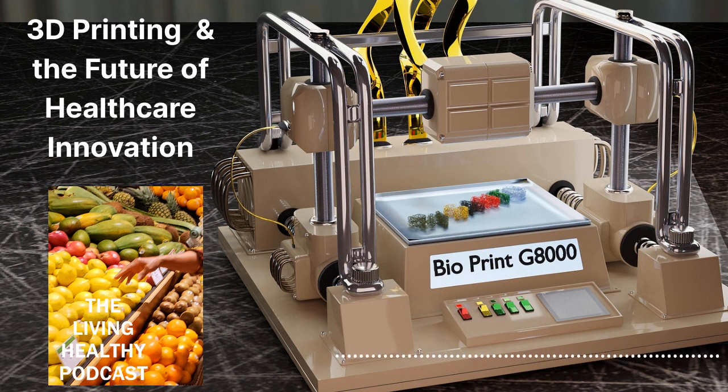As it stands, as of August of 2023, the FDA has already approved a sterilization process for 3D printed models and single-use instruments that will be used for procedures. The process cleans by using vaporized hydrogen peroxide under vacuum conditions. Surgical units already use this process, but this one in particular is specific for 3D printing.